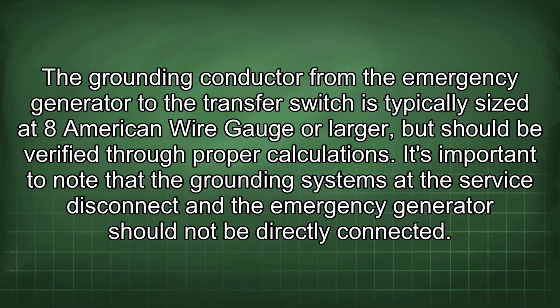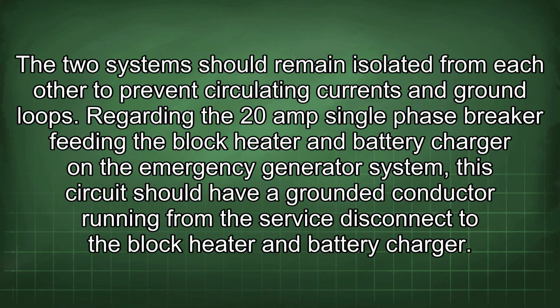It's important to note that the grounding systems at the service disconnect and the emergency generator should not be directly connected. The two systems should remain isolated from each other to prevent circulating currents and ground loops.